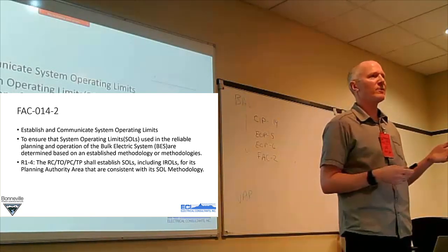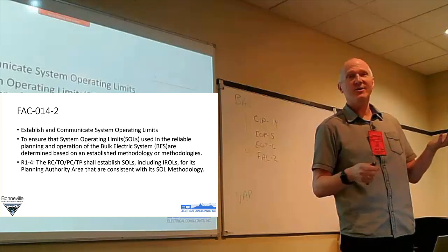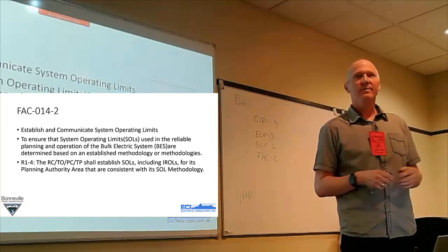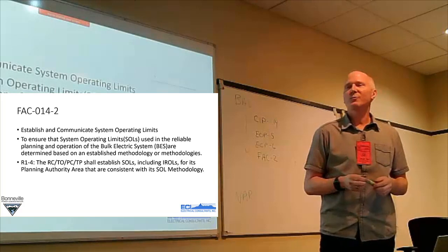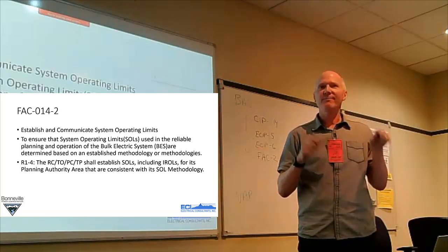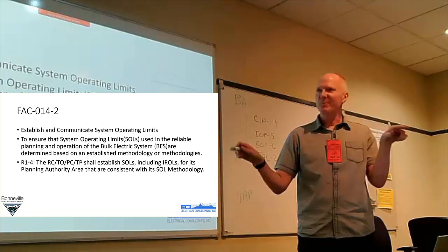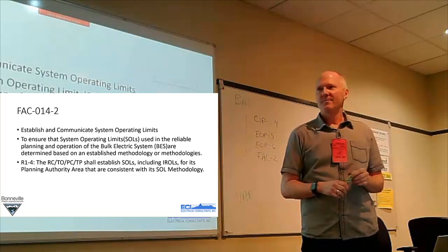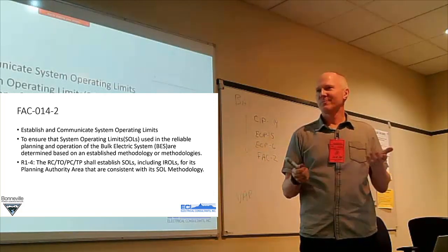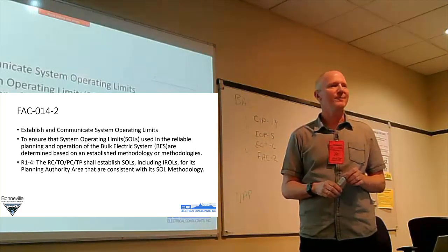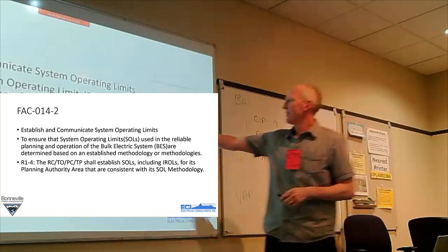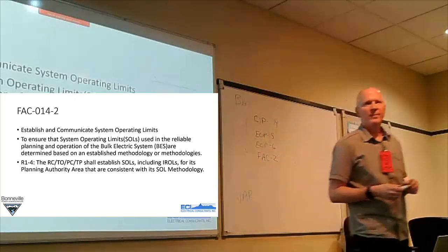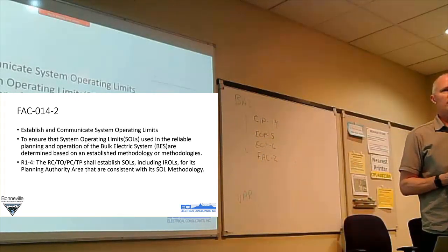Sometimes we all think of SOLs as, well, what's the thermal rating? Which is an SOL for the facility. And like she said, if you violate some of the SOLs, they can unzip the system, and those you have to call an IROL. Okay, so the really bad ones. Really angular stability bad. Oh, awesome. RC used to define it as having a load loss greater than 1,000 megawatts. Okay.